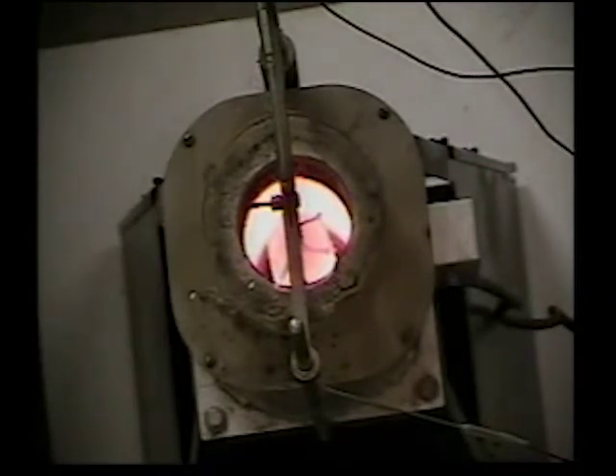As the test nears the 30-minute point, the second criteria is examined: a temperature delta of 30 degrees centigrade, which is defined as the peak temperature minus the temperature at the final 30-minute point. The maximum delta T is 8 degrees at the specimen center. The final criteria for test passage is examined after the specimen is removed and weighed.